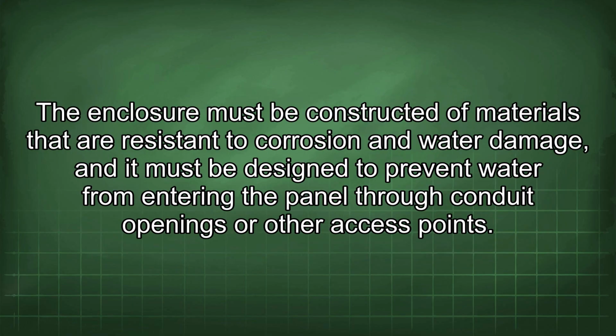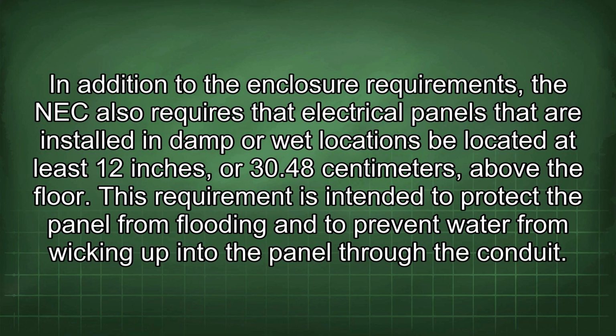The enclosure must be constructed of materials that are resistant to corrosion and water damage, and it must be designed to prevent water from entering the panel through conduit openings or other access points. In addition to the enclosure requirements, the NEC also requires that electrical panels that are installed in damp or wet locations be located at least 12 inches or 30.48 centimeters above the floor.